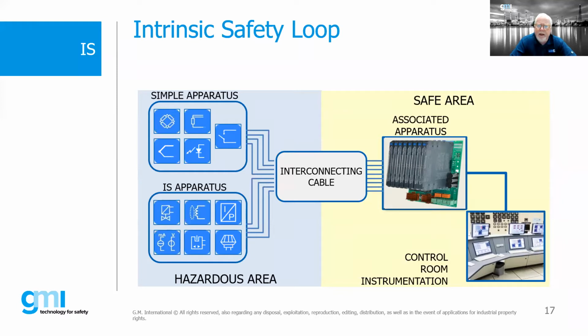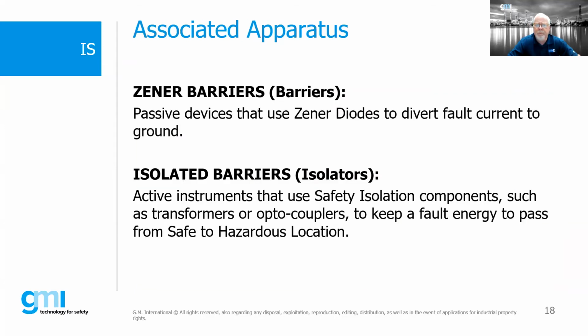Then we take a look at our cabling. Then we have the barrier - another term for that is associated apparatus. That's the terminology we use in our safety loop. We call a barrier an associated apparatus. And then, of course, the feed coming in from our instrumentation circuit. So that's our intrinsic safety loop, or what we'd call a control drawing, or potentially a descriptive system document.